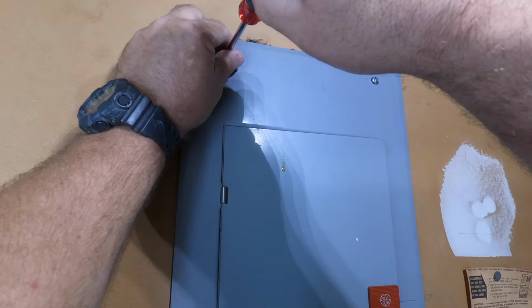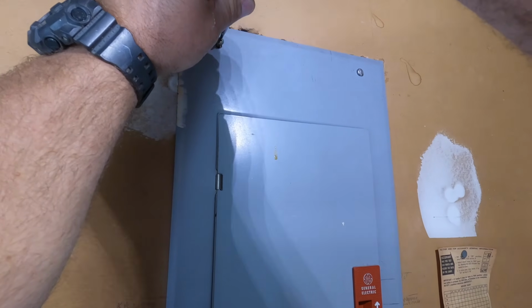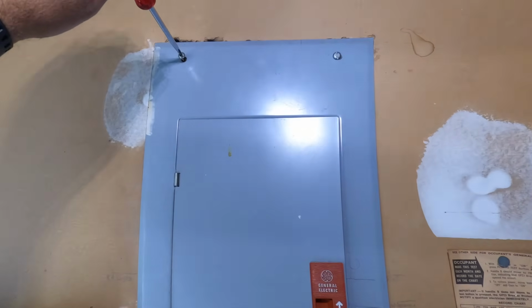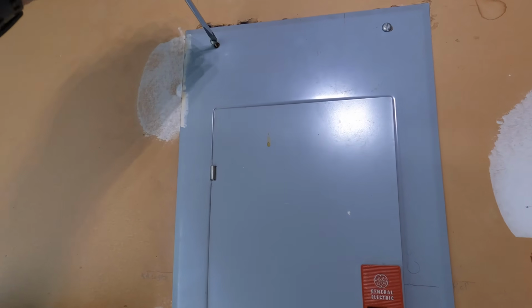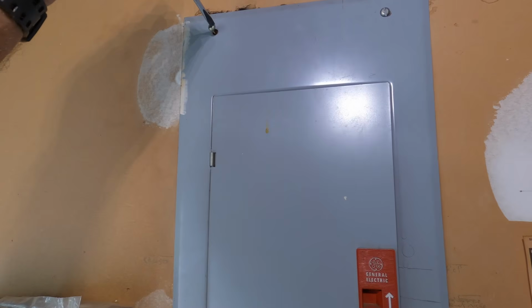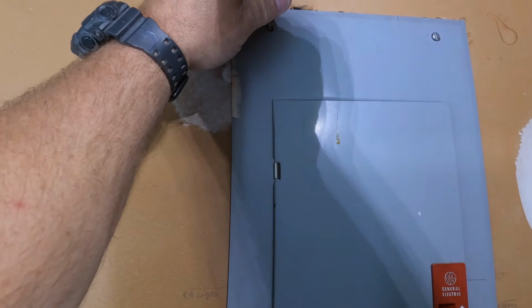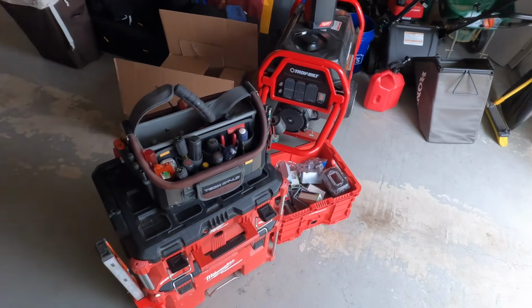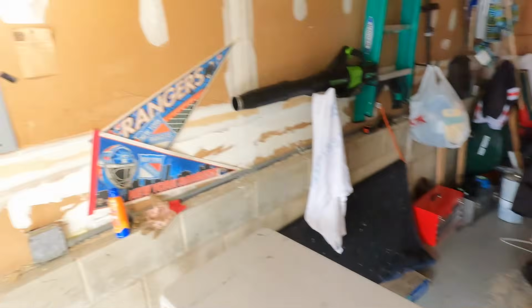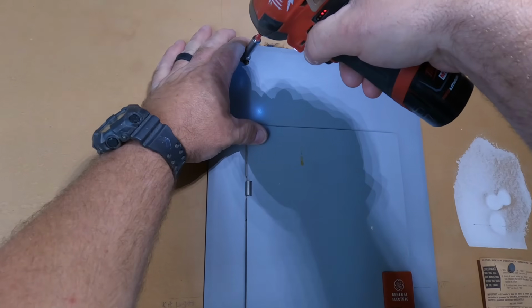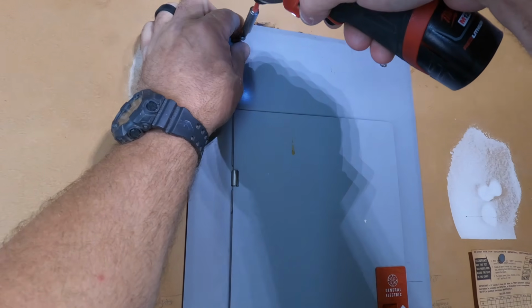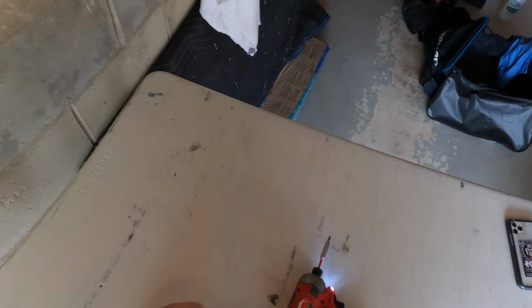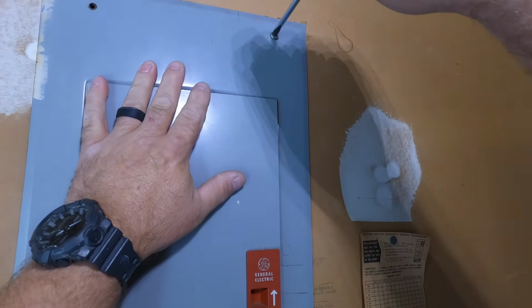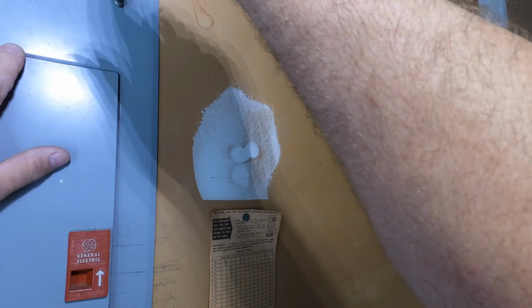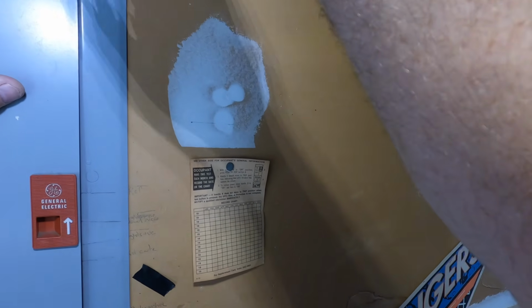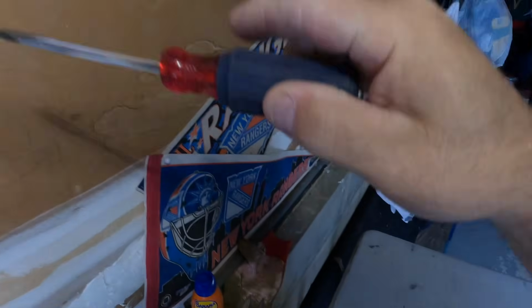And sure enough, it was that old GE panel with a non-GE circuit breaker inside the panel. The problem with the different brand breaker inside the GE panel is the circuit breaker was making no connection to the bus bar, or was very loose rather. As soon as I took the panel cover off, there was no power at that particular breaker. Then when you pushed it in just a little bit with the cover off, it came on. So obviously it wasn't making a good contact with the bus bar, and that's very dangerous, especially with something that has a larger load than a modern day refrigerator, which isn't very much at all.